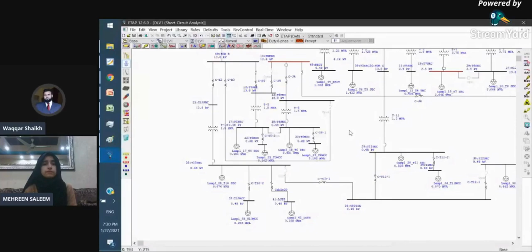Now, if you go into the short circuit mode, the question is symmetrical faults or asymmetrical faults. When I say symmetrical faults, you mean triple line fault or triple line to ground fault. Normally when we say symmetrical faults, we are interested in the worst case faults, because triple line faults or triple line to ground faults are the worst case faults. So when you run the simulations considering the option run three-phase device duty, it will allow you to run symmetrical, three-phase faults. But if you want to go for asymmetrical faults like line to ground fault, double line fault or double line to ground fault, then you should not select this option when running the simulation.